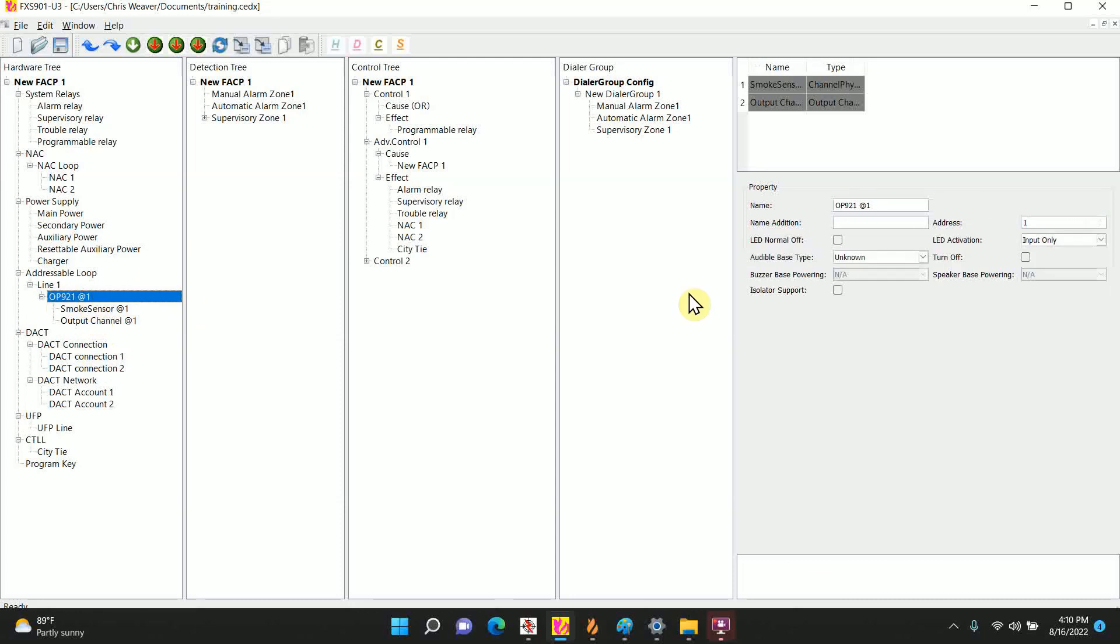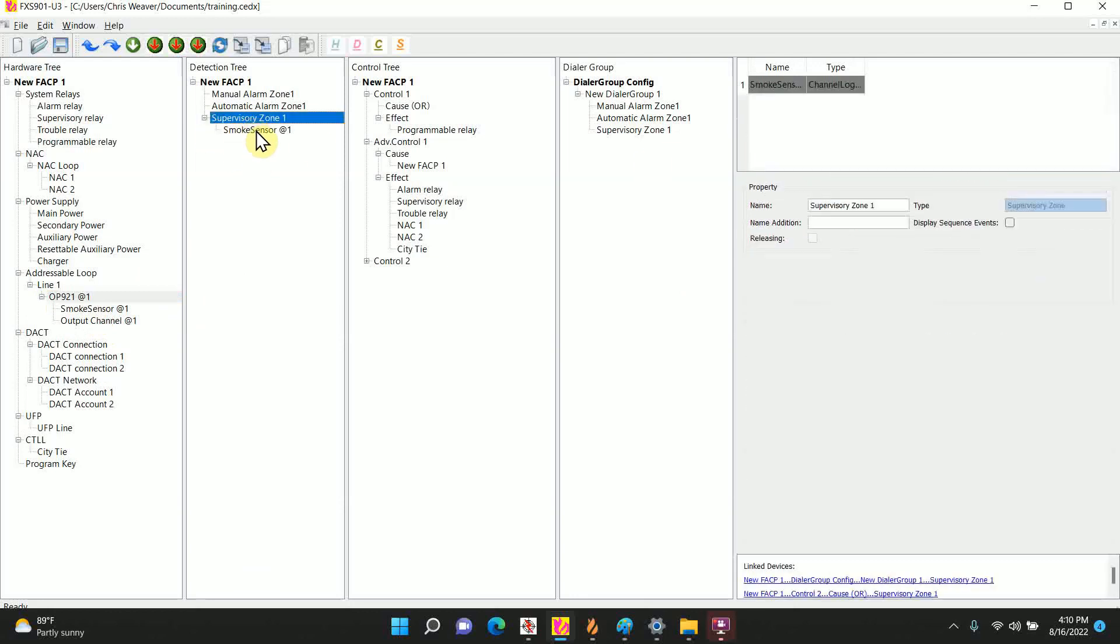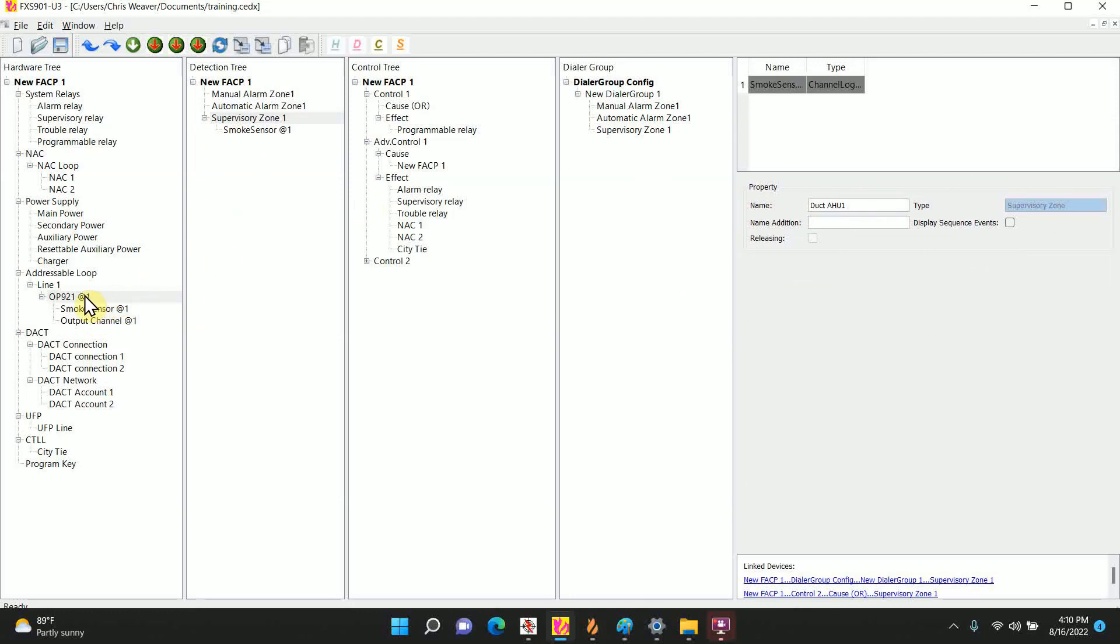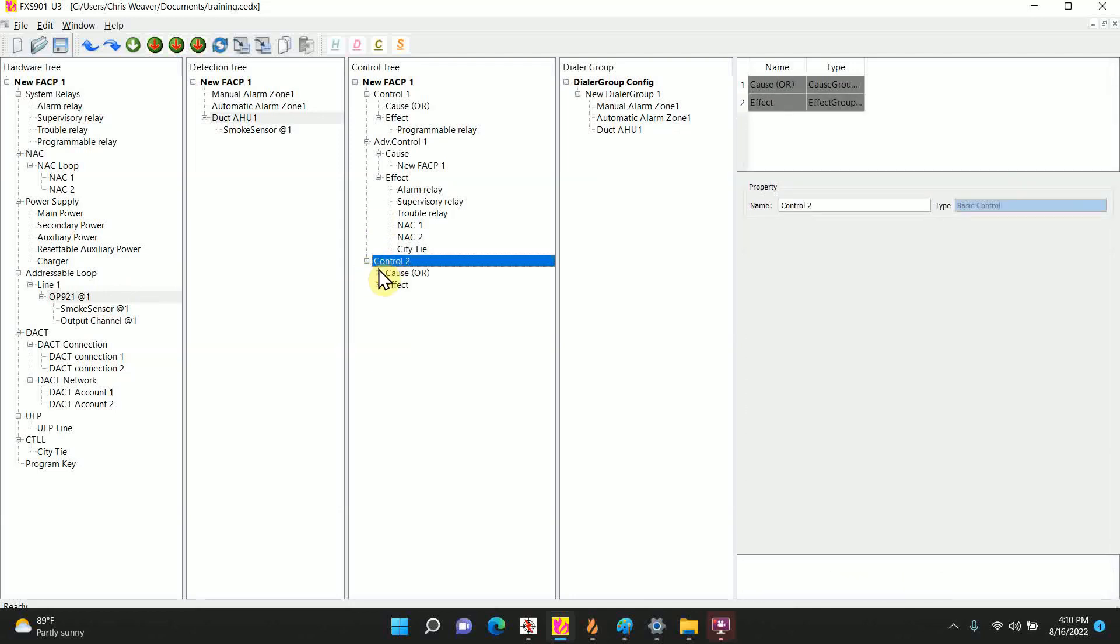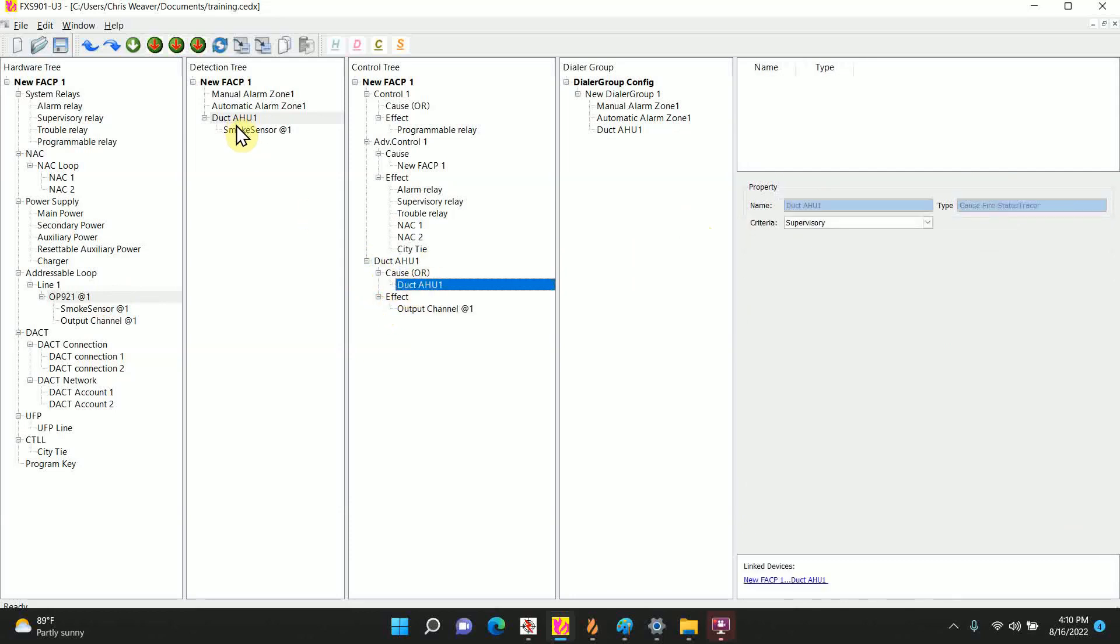Of course here's where you would change your description. I'll just call this duct air handler 1. Same thing here in the supervisory zone, I'll call it duct air handler 1. Now the nice thing about the 901 program is for your most basic duct detectors, it's going to be a standalone unit. If you look here, it automatically added the control. So you've got control 2. We can name this duct air handler 1 just for good labeling. And automatically in the cause and effect, it put the supervisory signal as the cause and the output as the effect.